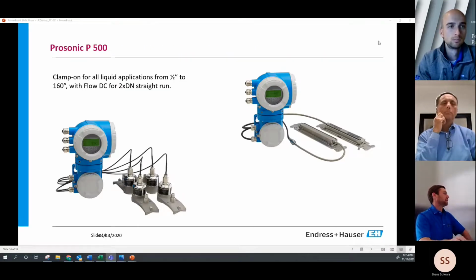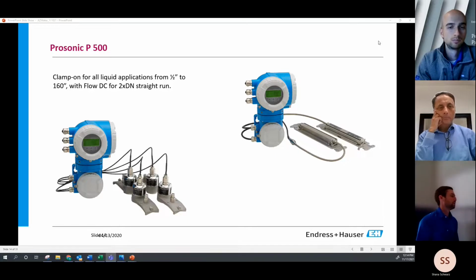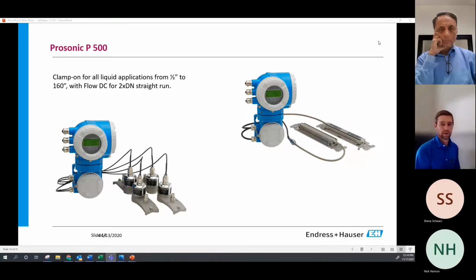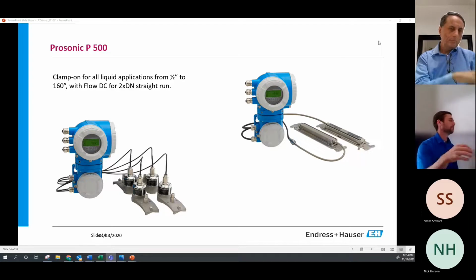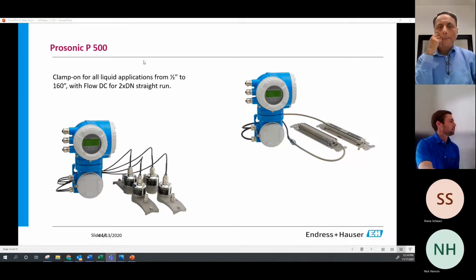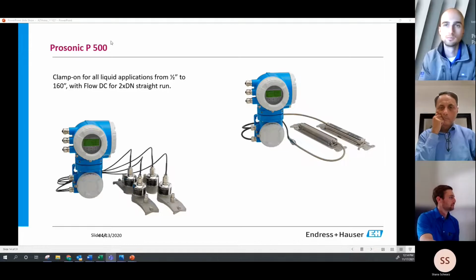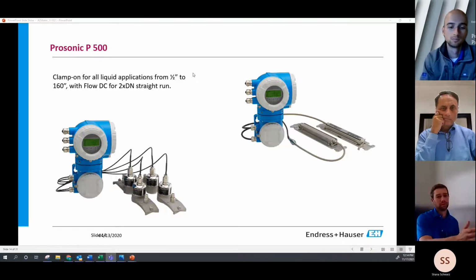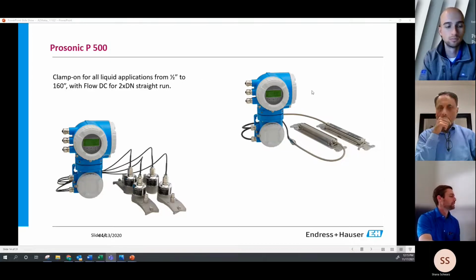So E&H took a look at their ultrasonic solutions and put together a device that uses multiple transducers as well as some more robust firmware to average more of the flow profile, very similar to the mag meter, effectively taking more information and doing more with that information. So the new ProSonic P500 fits the same form factor as far as straight run requirements as the mag meter we were talking about. The only caveat being that you do need 2 pipe diameters upstream and 2 pipe diameters downstream. Sizes are available from 1/2 inch to 160 inches.